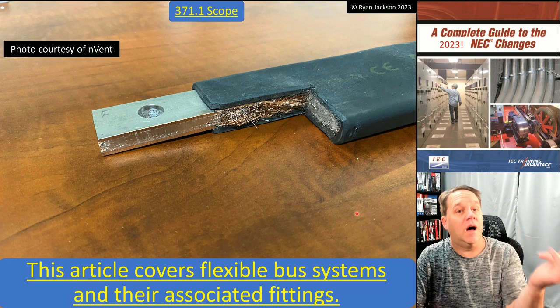This is a design that nVent created to show what you might use this product for. Here I've got this massive medium voltage transformer, maybe stepping it down to 480 volts in my building, and I'm going to run insulated flexible bus over to my switchboard. You can see we run it up onto a cable tray, then we have some support brackets. We run this flexible bus, hit a transition box, go down here, and bolt it right into the lugs of the switchboard or switchgear.